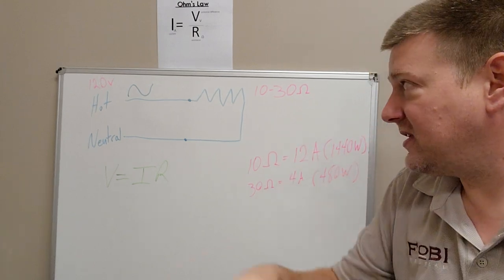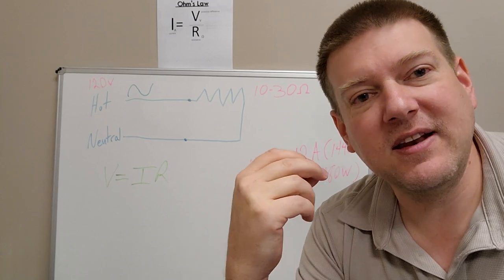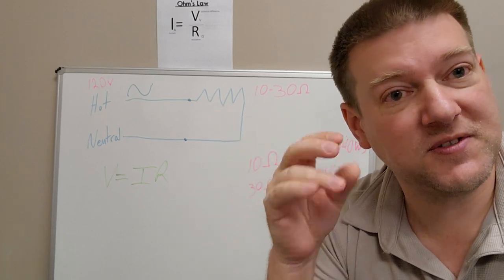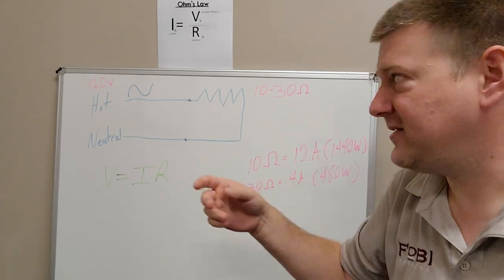Now the cool thing about heating elements is that they're almost always running at line voltage. Some heating elements in medical equipment will run off of pulse DC, but usually for most devices they run at line voltage.